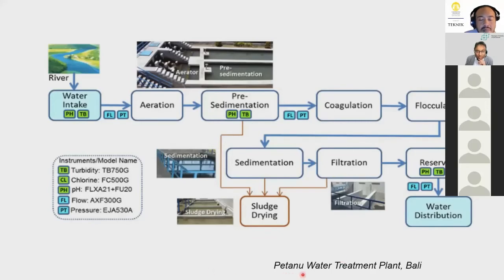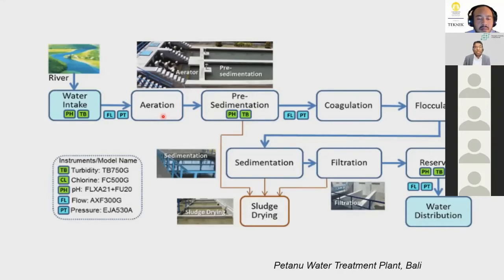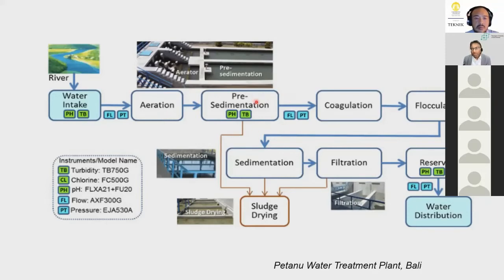An example treatment plant diagram from Petanu Water Treatment Plant in Bali is shown. It includes aeration — used to remove ammonia, nitrogen, or for groundwater treatment to oxidize ferrous iron (Fe²⁺) to ferric (Fe³⁺) — followed by pre-sedimentation if necessary, coagulation and flocculation, sedimentation, filtration, reservoir, and distribution, with sludge taken to a sludge processing system.